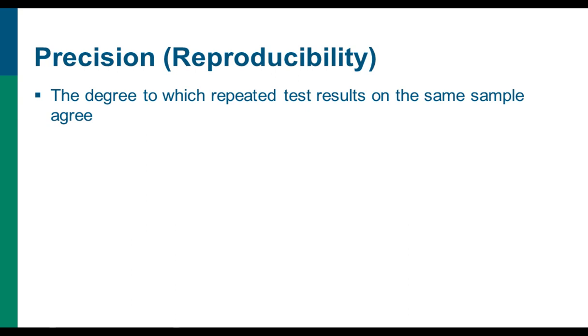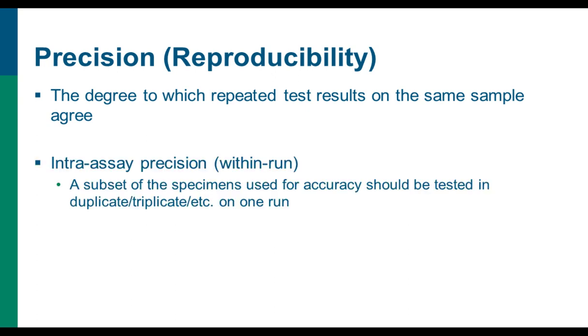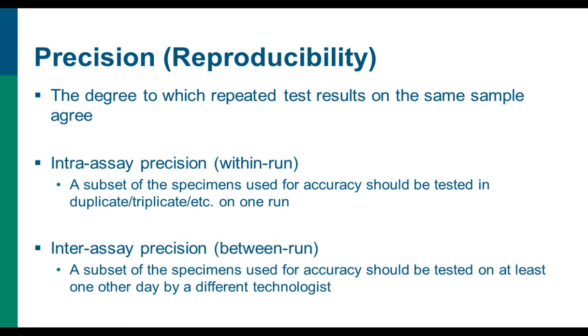In addition to accuracy, one of the requirements for verification validation is precision or reproducibility, and that's looking at if you take the same sample and repeat it multiple times, does it still give the same result? And there's two types of precision. There's within-run or intra-assay precision, which is where you want to test the specimen in multiples on one run. So, at one point, instead of running it in singlet, run it in duplicate, triplicate, etc.